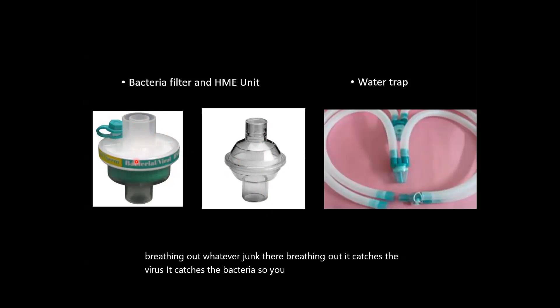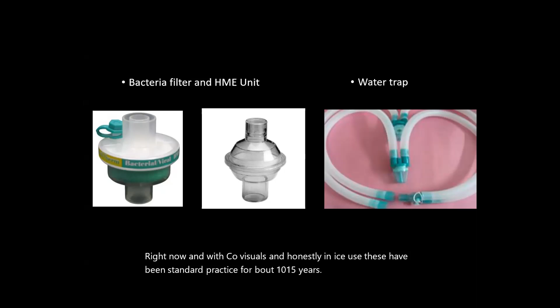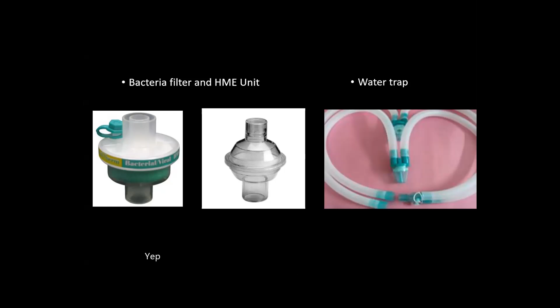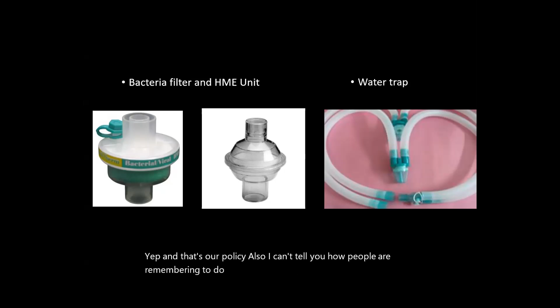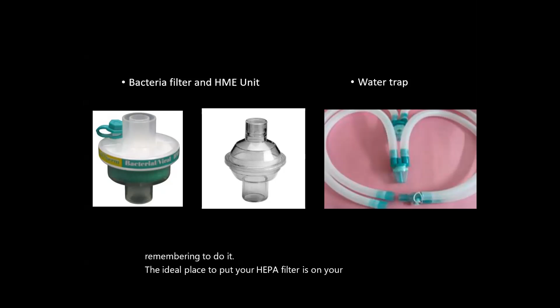Right now with COVID, you'll see, and honestly in ICUs, these have been standard practice for about 10, 15 years. Yeah, so our protocol now is whenever we bring a code for somebody, we have to put the HEPA filter on because they are assuming that they are going into cardiac arrest due to COVID. Yep, and that's our policy also. I can't tell you how much people are remembering to do it. The ideal place to put your HEPA filter is on your exhalation port, but I've seen it put on both the exhalation port and inhalation port, between the BVM and the mask.